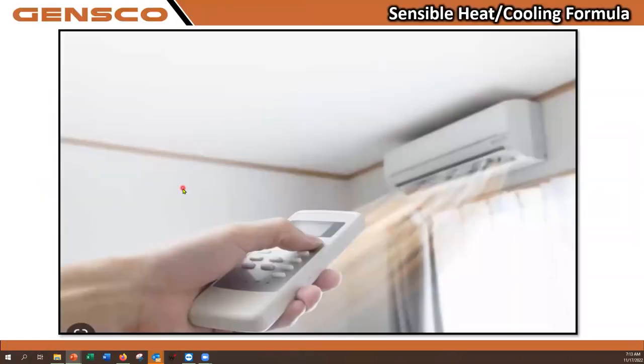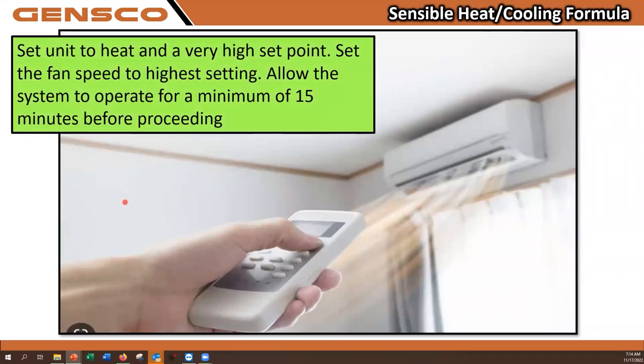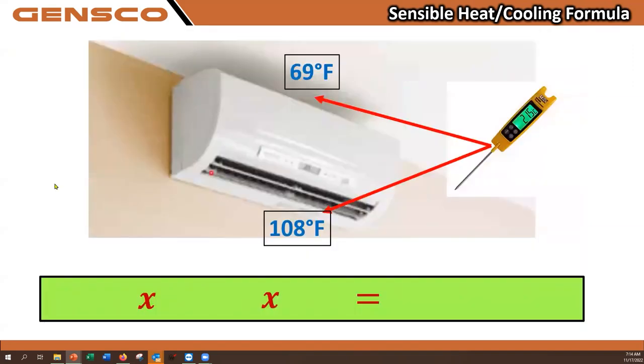Now, for our actual test, we're going to turn this unit on in heat mode and set the set point as high as we can, because if we can get it more than 4 degrees from actual temperature, the unit will go to full speed. So we set it as high as we can so it doesn't satisfy or get within that 4-degree band from the actual temperature. We're going to allow this to run for 15 minutes, and we're going to keep that fan on high speed. Then we take a measurement at the end of that time period, 15 to 20 minutes.